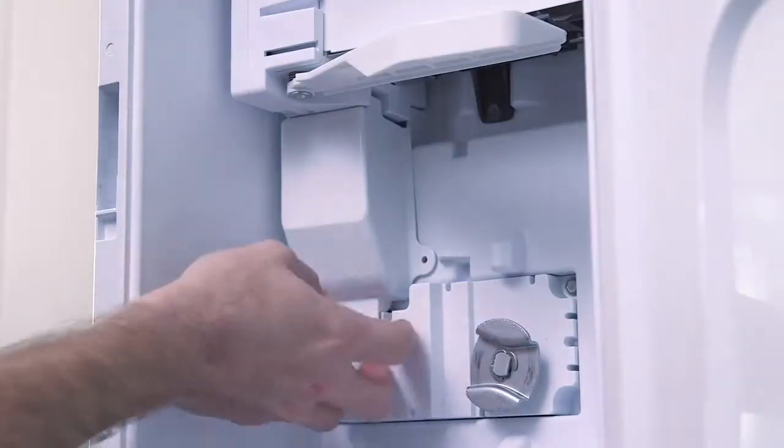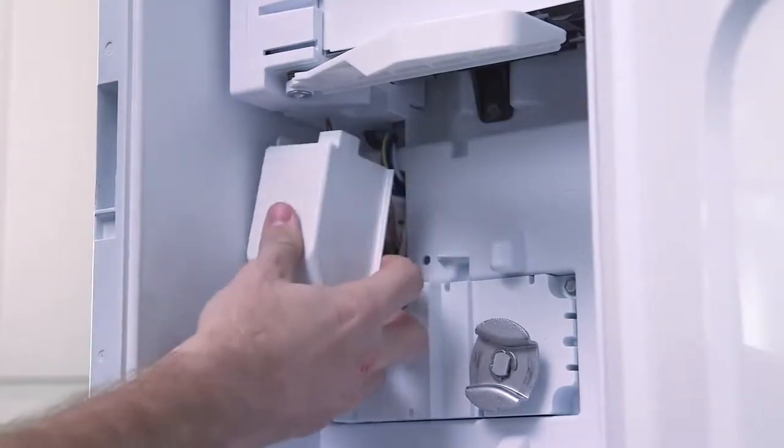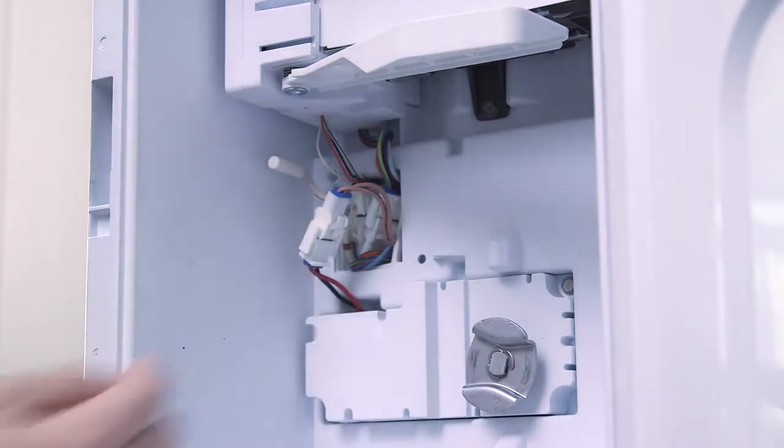Unscrew and remove the 5/16 inch hex screw head that holds the wire harness cover in place. Lift the bottom of the wire harness cover and remove it. Note that the thermistor will automatically disconnect from the cover when removed.